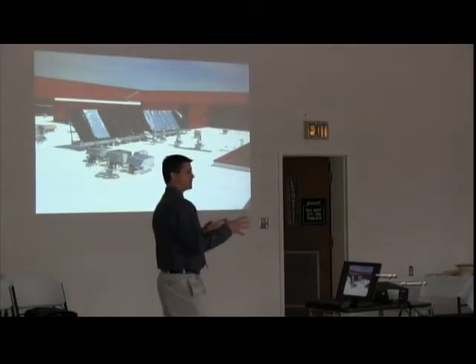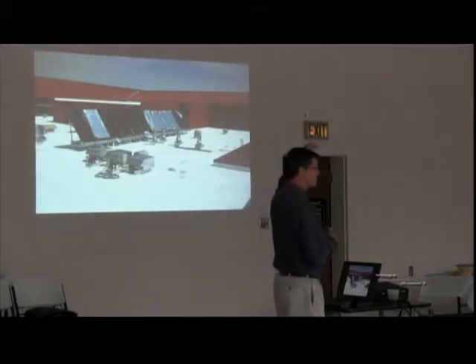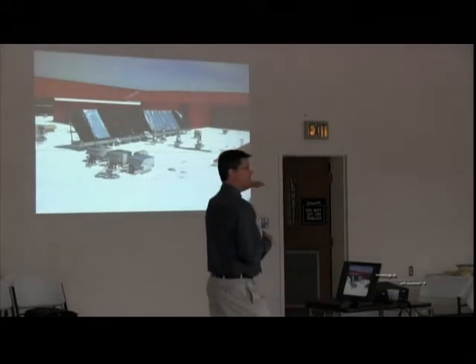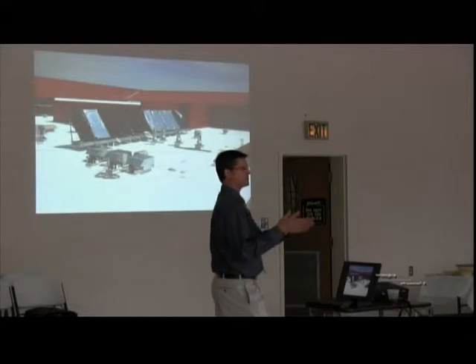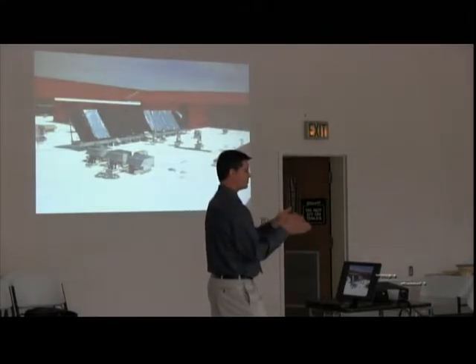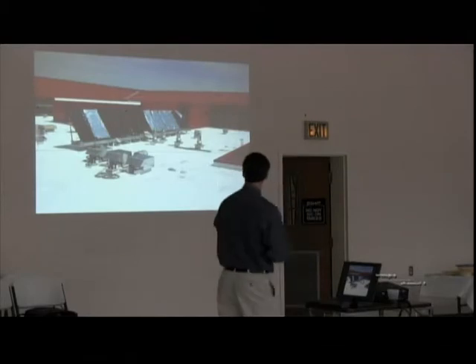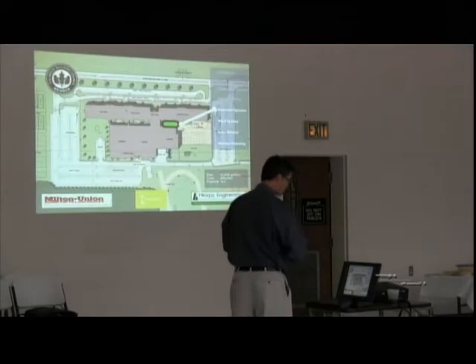There's a traditional gas-fired boiler, but the water that goes into that boiler is the preheated water from the solar thermal system. So instead of natural gas heating up 65-degree water to 140 degrees, it's heating up 115 to 120 degree water to 140 degrees, because the amount of energy that it takes to change the temperature of water 40 degrees, no matter how hot or cold, is always the same. But if you're moving at 40 degrees, you're using a certain amount of gas. But if you're moving 80 degrees, you're using a lot more gas. So the solar thermal helps alleviate gas usage.